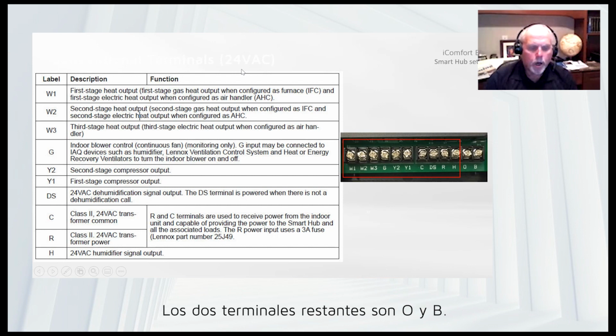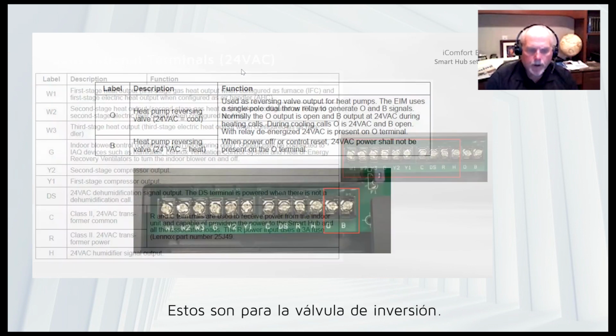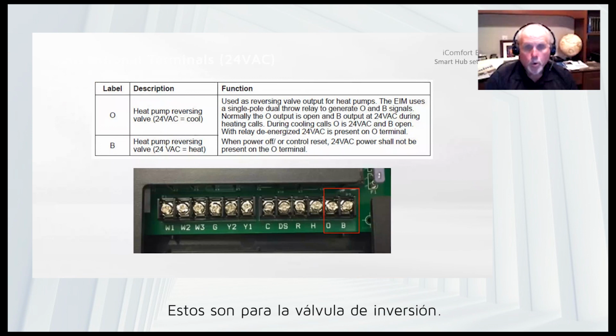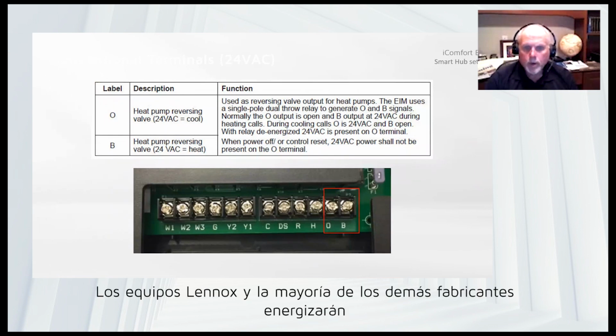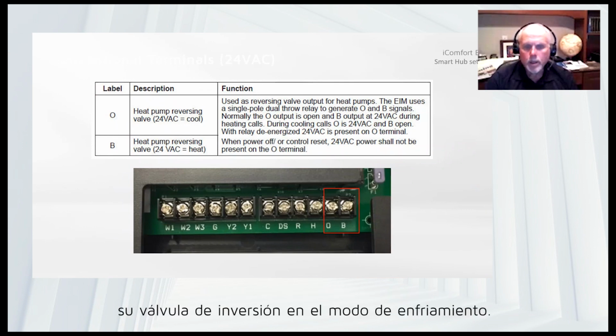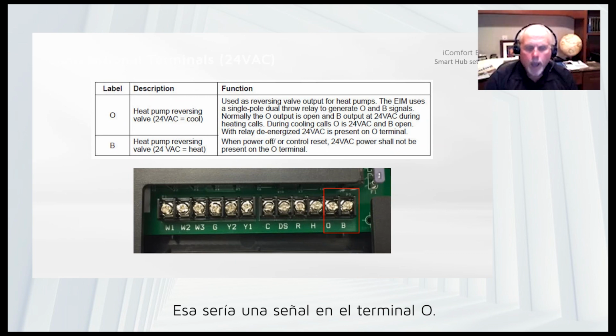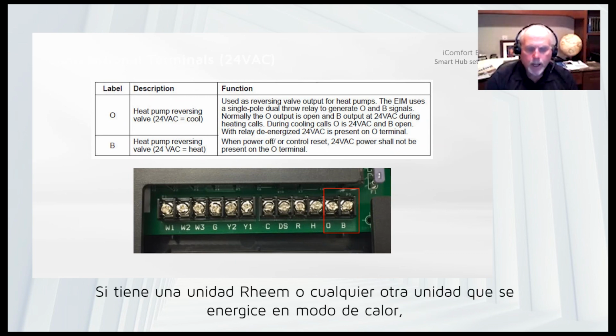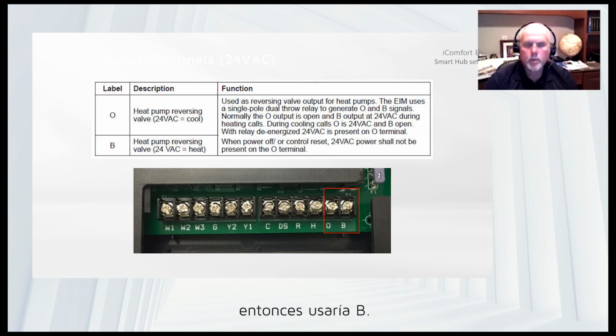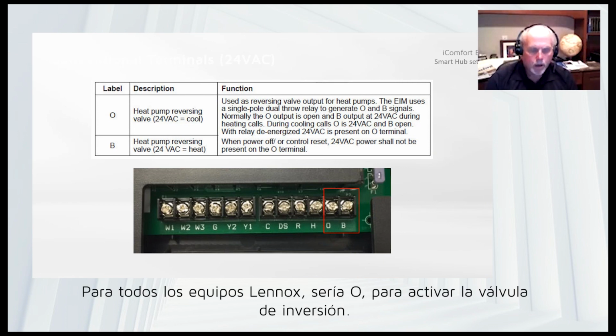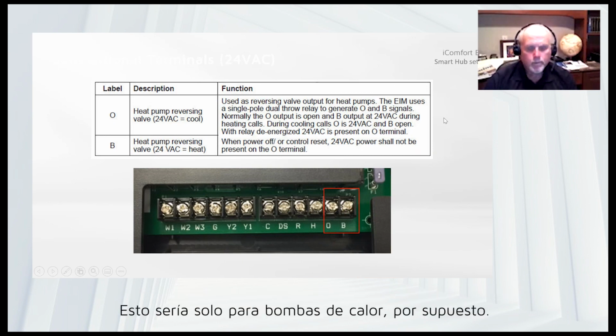The two remaining terminals are O and B. This is for your reversing valve. Lennox always uses O. Lennox equipment and most other manufacturers will energize their reversing valve in the cooling mode, so that would be an output on O. If you have a Rheem unit or any other unit that would energize in heat mode, then you would use B. But for all Lennox equipment, it would be O to O on your equipment for the reversing valve. This would be for heat pumps only, of course.